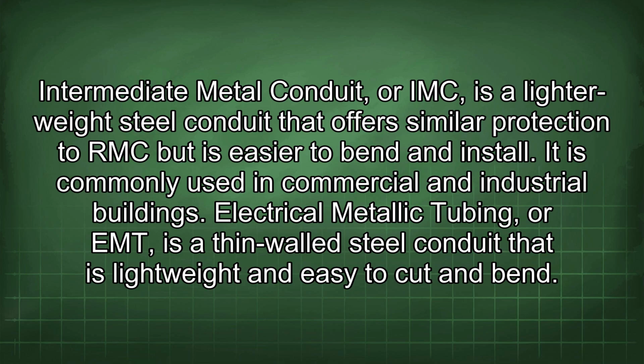Intermediate metal conduit, or IMC, is a lighter-weight steel conduit that offers similar protection to RMC but is easier to bend and install. It is commonly used in commercial and industrial buildings. Electrical metallic tubing, or EMT, is a thin-walled steel conduit that is lightweight and easy to cut and bend.